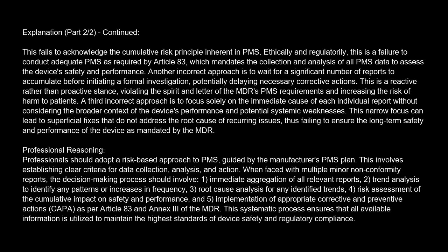2. Trend analysis to identify any patterns or increases in frequency. 3. Root cause analysis for any identified trends. 4. Risk assessment of the cumulative impact on safety and performance. And 5. Implementation of appropriate corrective and preventive actions. As per Article 83 and Annex III of the MDR, this systematic process ensures that all available information is utilized to maintain the highest standards of device safety and regulatory compliance.